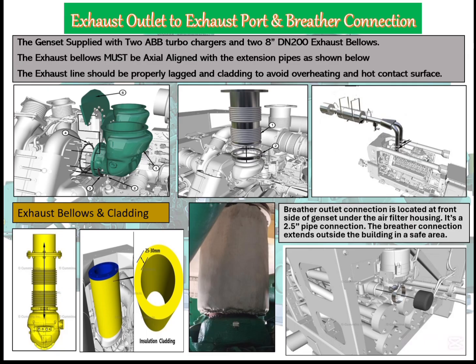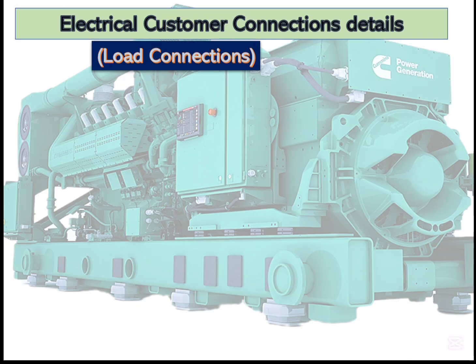So with this one, all our mechanical connections have been completed, where we discussed the coolant, LT and ST, in and out. We discussed dual in and out, the valve, fill and drain. We also discussed coolant vent lines that go to the expansion tank. Then we also discussed the fuel line, then exhaust lines and breather lines. So with this one, our mechanical connection has been completed. So let's move on to electrical connections.